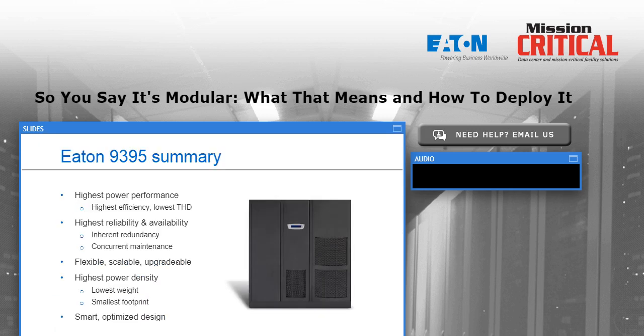Here's an example of one. This particular UPS is about 6 feet tall and a little under 6 feet wide, and it has the capability of adding extra 300 kilowatt power modules to the existing one that they start off with. So they can deploy that extra capacity on day one. It would add about another 24 inches to the width of the UPS, or they can deploy that extra capacity if and when needed, and if necessary, any extra battery cabinets could be added to the system. And the idea here is to provide highly efficient operation.